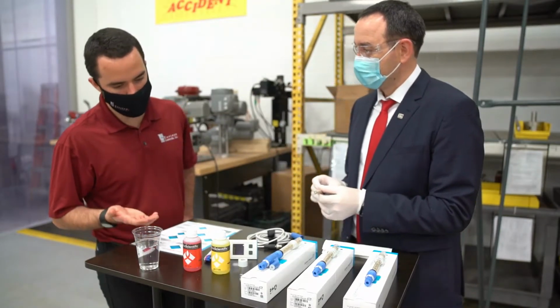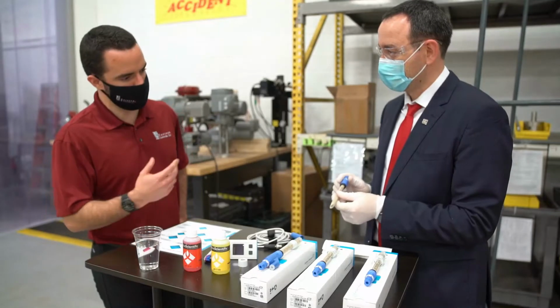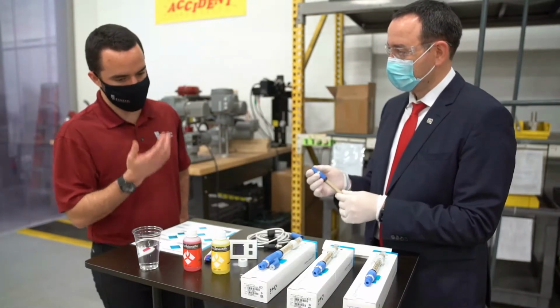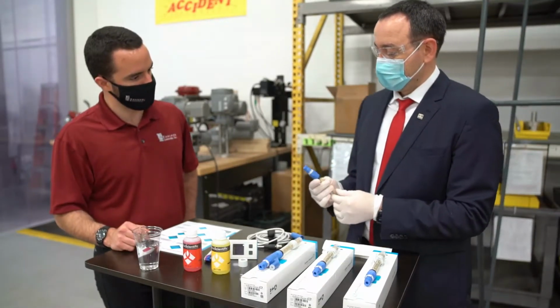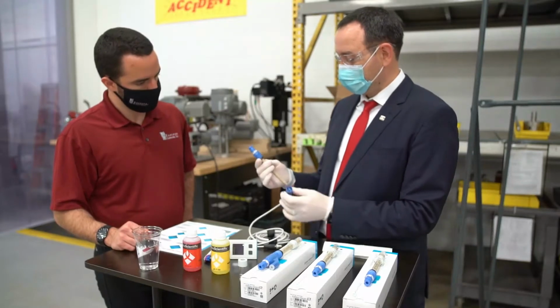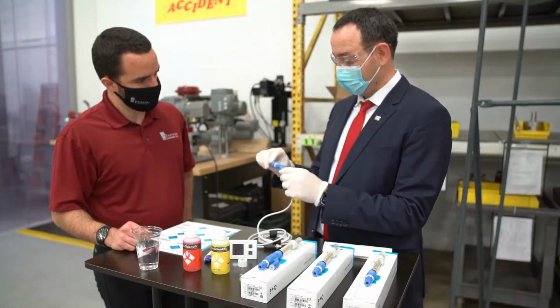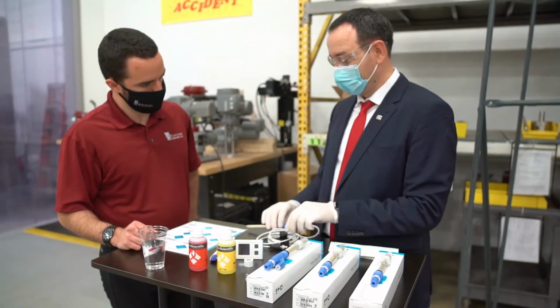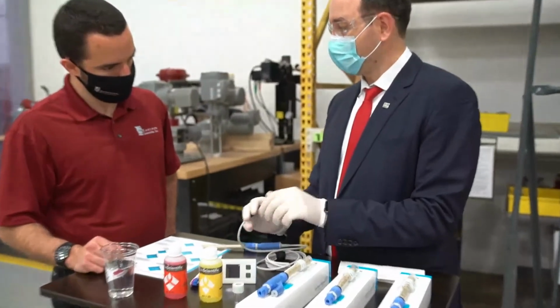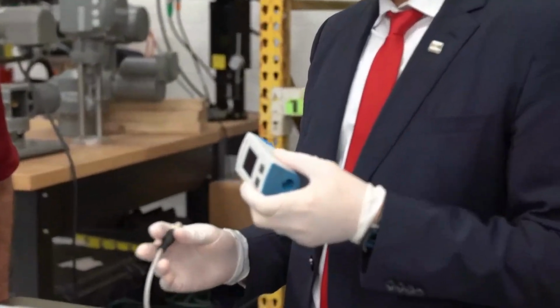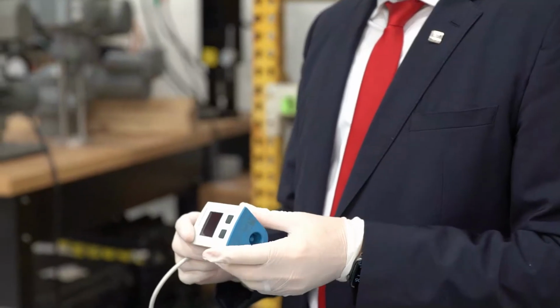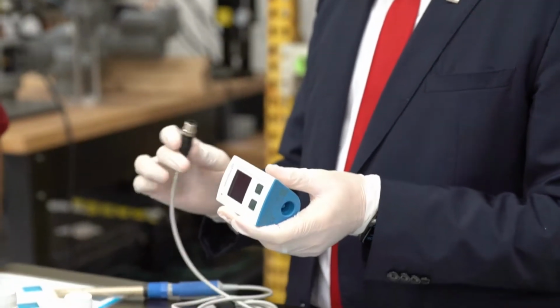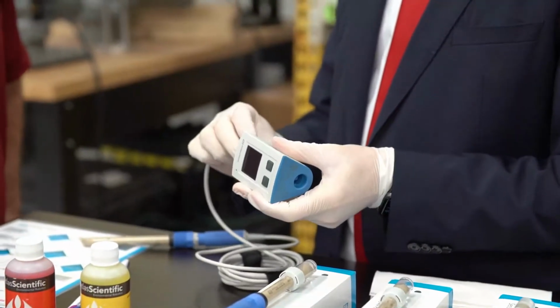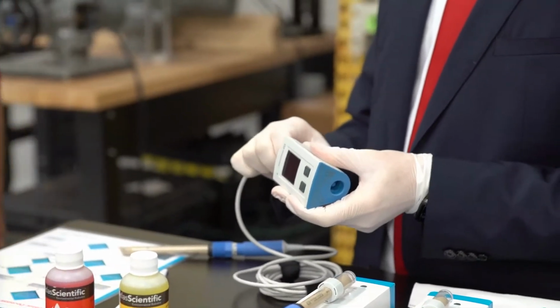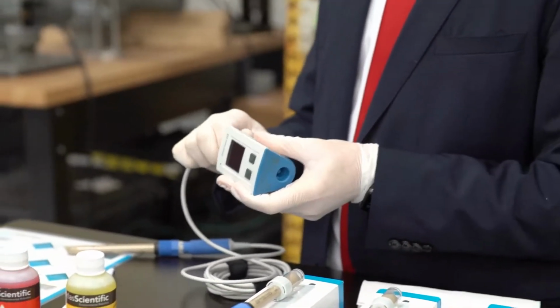Okay, but what can we use to verify the reading? Once the probe is clean, how do we verify the reading? How do we calibrate it? So we need to connect the probe to a transmitter, either with a cable or directly. For that we use a portable transmitter. Okay, the portable transmitter. See, at our site, we only have the Liquiline CM444s. I'm not familiar with this portable.